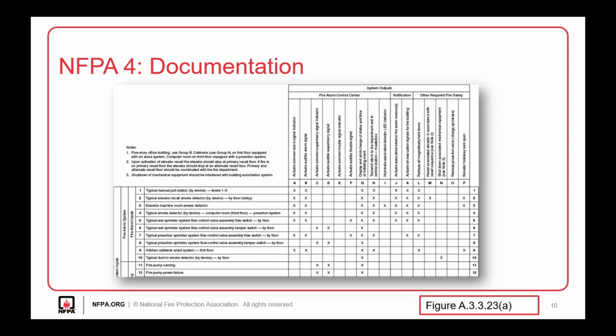So let's use a flow switch, for example. If you flowed water, that would be the change of status for that flow switch. But maybe you simulated it. Maybe you manipulated the contacts of that flow switch in order to send the signal to the fire alarm. So you need to note that in the sequence of operations.